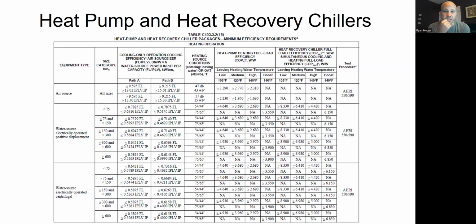Both of these types of things, heat pump chillers and heat recovery chillers, have made their way into the International Energy Conservation Code. That's how you know you're big time. That's how you know you made it, is when they start policing you for your efficiency. Up until prior to 2021 code, I think, or 18, I'm trying to think of which one it jumped into, but up until that point, this did not exist. So when you put in a heat recovery chiller, you had to make it match the efficiency in the tables for the regular chillers, which was hard to do. And if you did a heat pump chiller, then you had to pretend that it was like a small air side heat pump and try to make it match that. But now it's actually a defined thing for both of these.